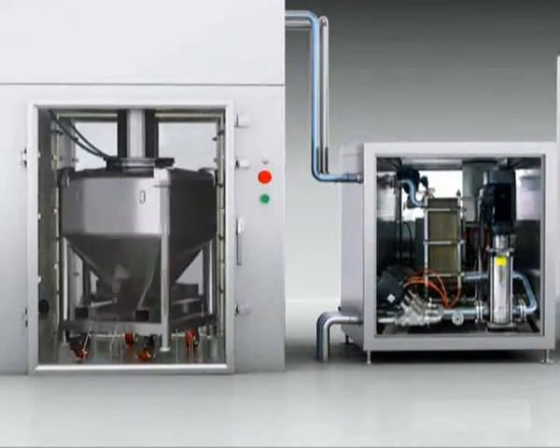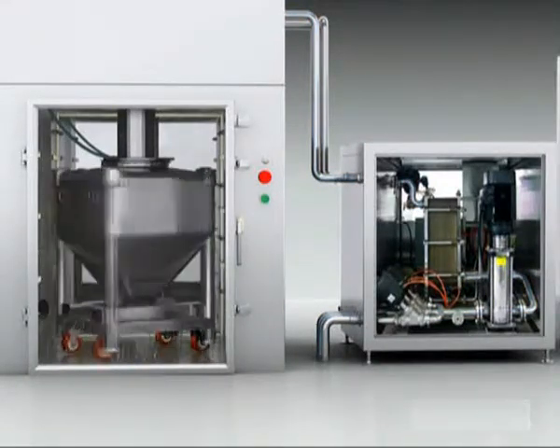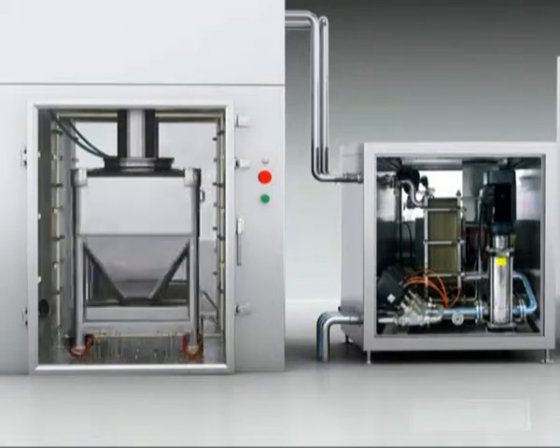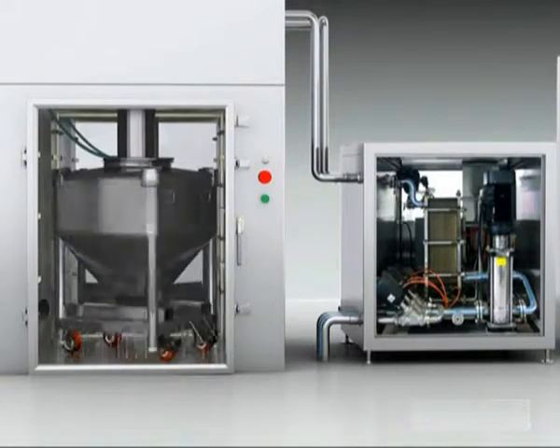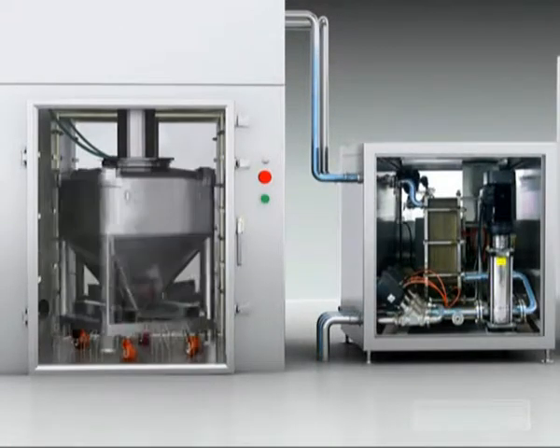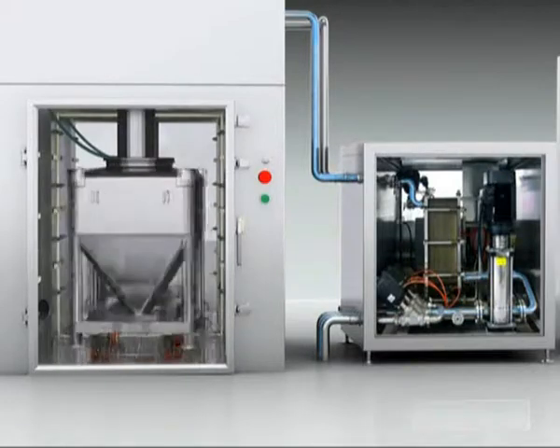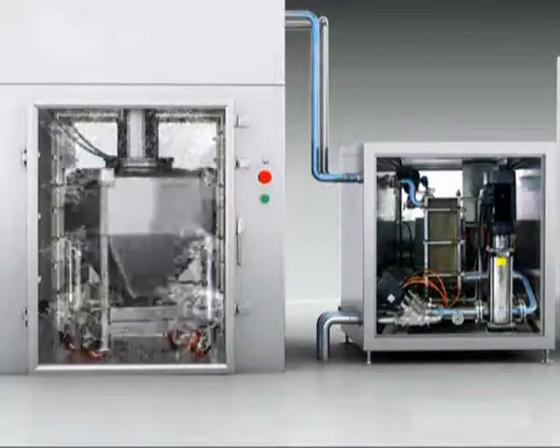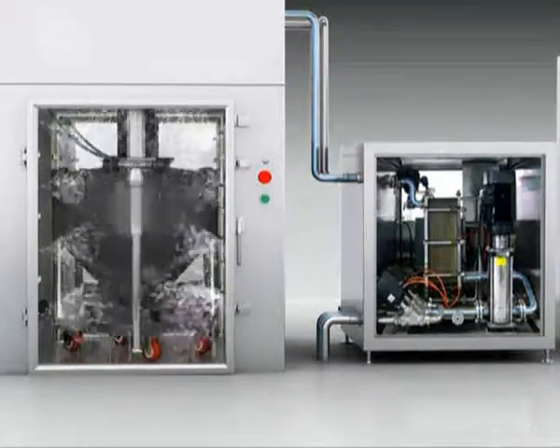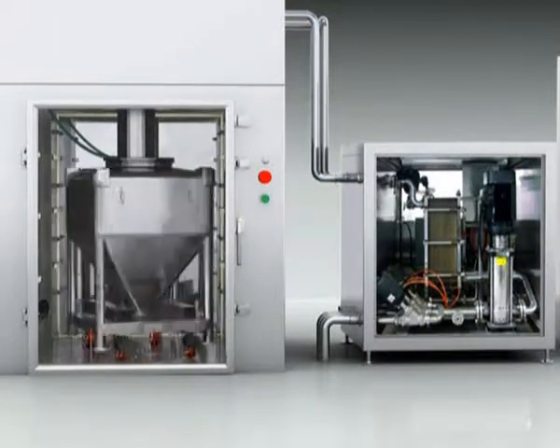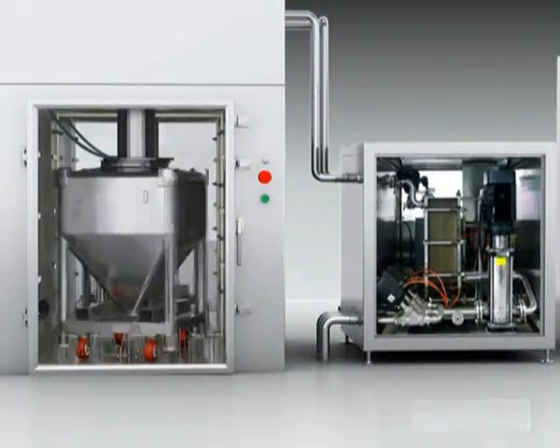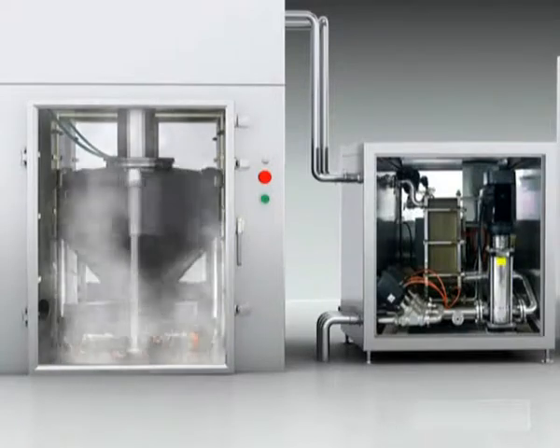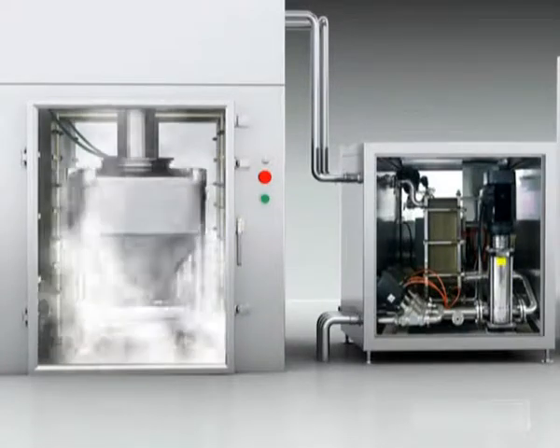The pure water pressure is raised by the boost pump inside the pump station and flows through the piping to the top washing board and the nozzles on the washing chamber walls for internal and external surfaces final cleaning. When the washing is finished, the system loads automatically the compressed air blow procedure. It blows out the remaining pure water inside of the pipes. Upon finishing with compressed air blow, drying cycle starts automatically.